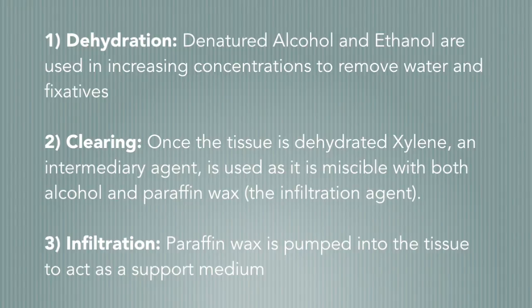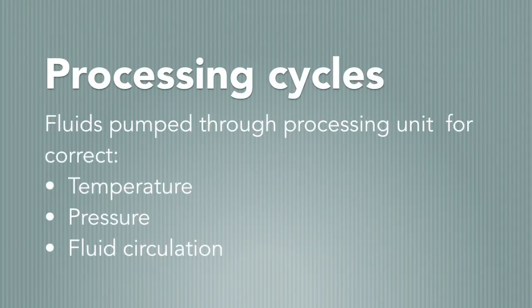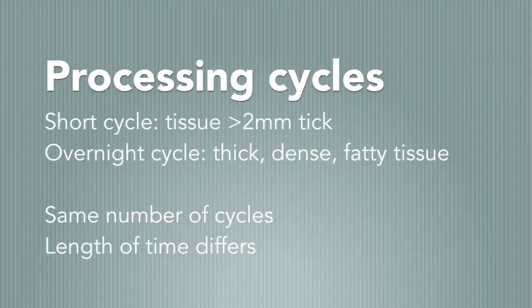During infiltration, paraffin wax is pumped into the tissue to act as a support medium. The fluids are pumped in and out of the processing unit in a controlled manner for correct temperature, pressure, and fluid circulation. Processing of tissue is done either in a short cycle, for tissues up to 2mm thick, or an overnight cycle, for thicker, denser, or fattier tissue. The number of cycles is often the same for both; however, the length of time the tissue is exposed to each fluid is what differs between cycles.